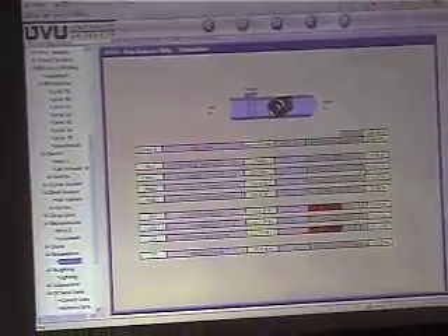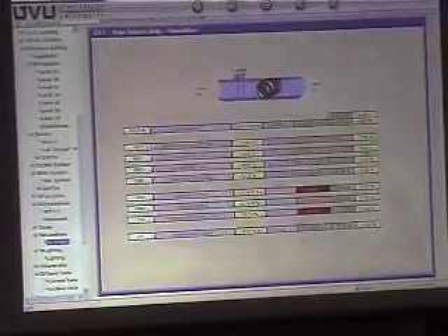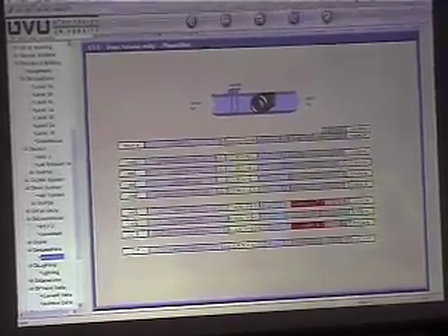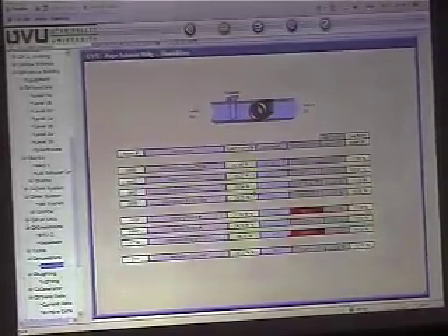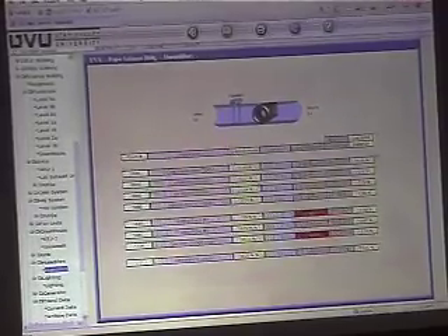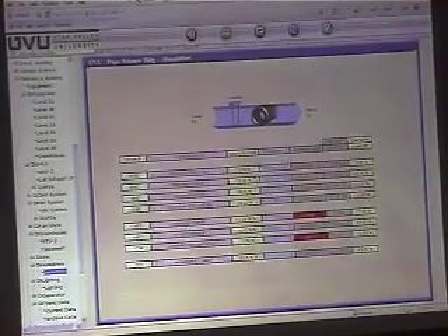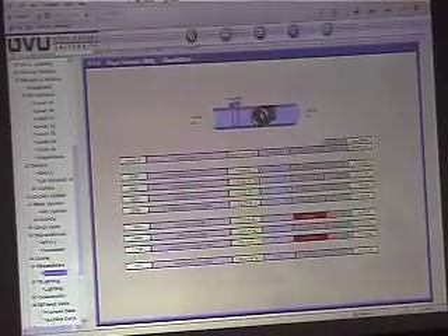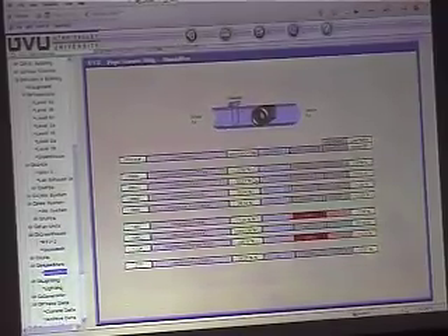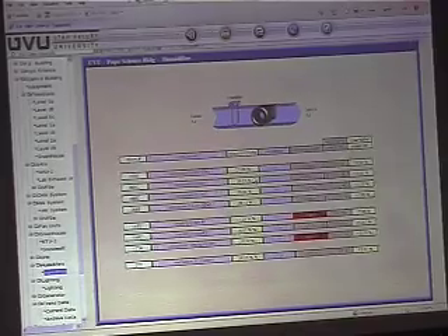We've got alarm points here. If the humidity levels get below this range or above that range, it'll alarm that the room's outside of that. So we're sending a 4 to 20 milliamp signal to maintain a humidity set point, or it's sending us. We're sending a signal that represents the space humidity, and then it uses that signal to modulate itself. So it doesn't have a remote sensor. Okay, got it. We're the remote sensor, so it uses our signal to know what its humidity is in the room.